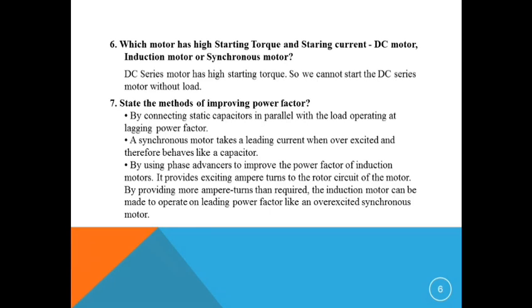Next question: state the methods of improving power factor. By connecting static capacitors in parallel with the load operating at lagging power factor. A synchronous motor takes a leading current when overexcited and therefore behaves like a capacitor.